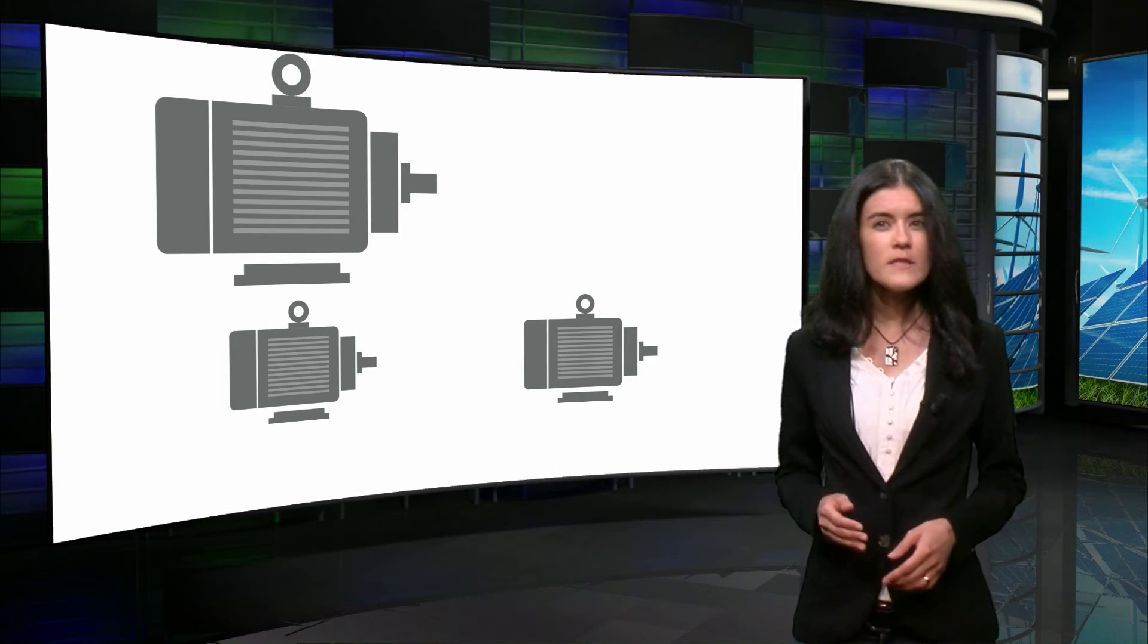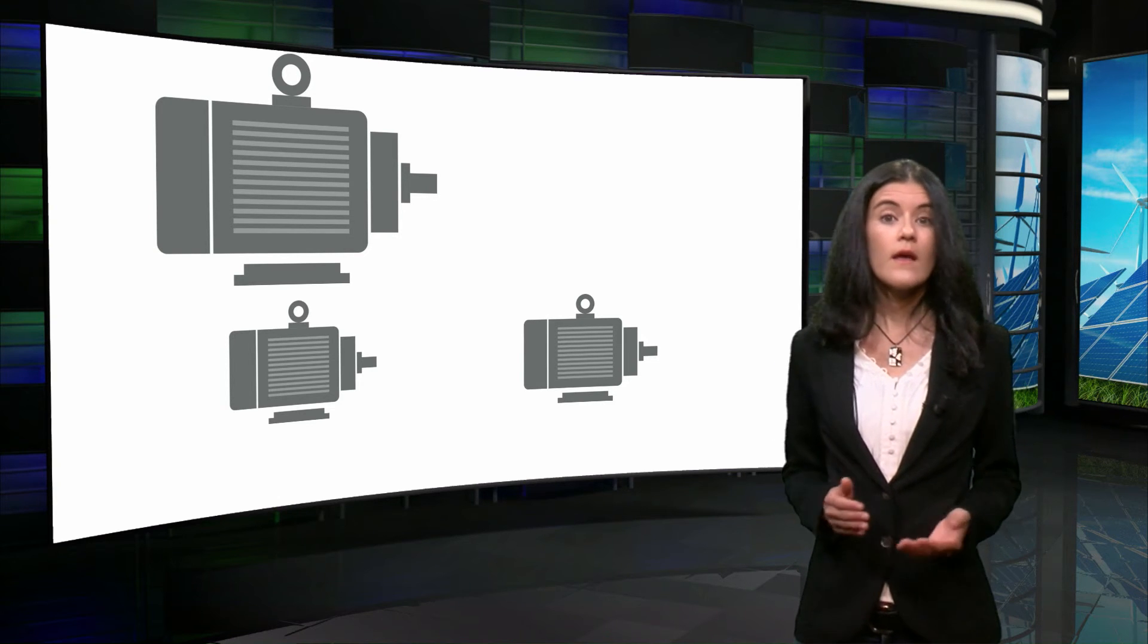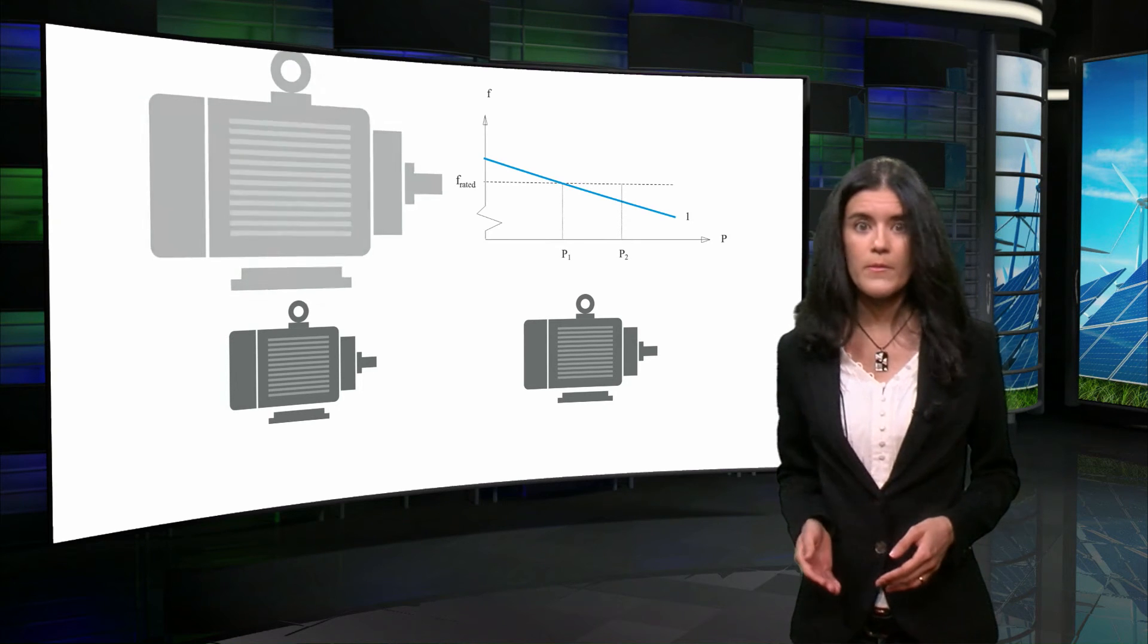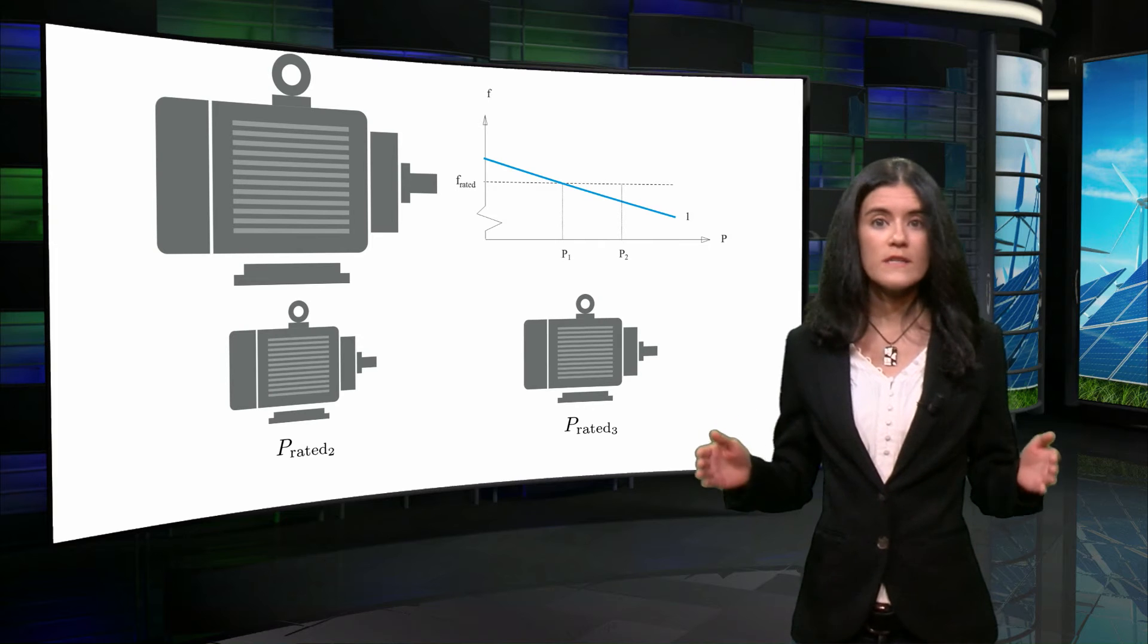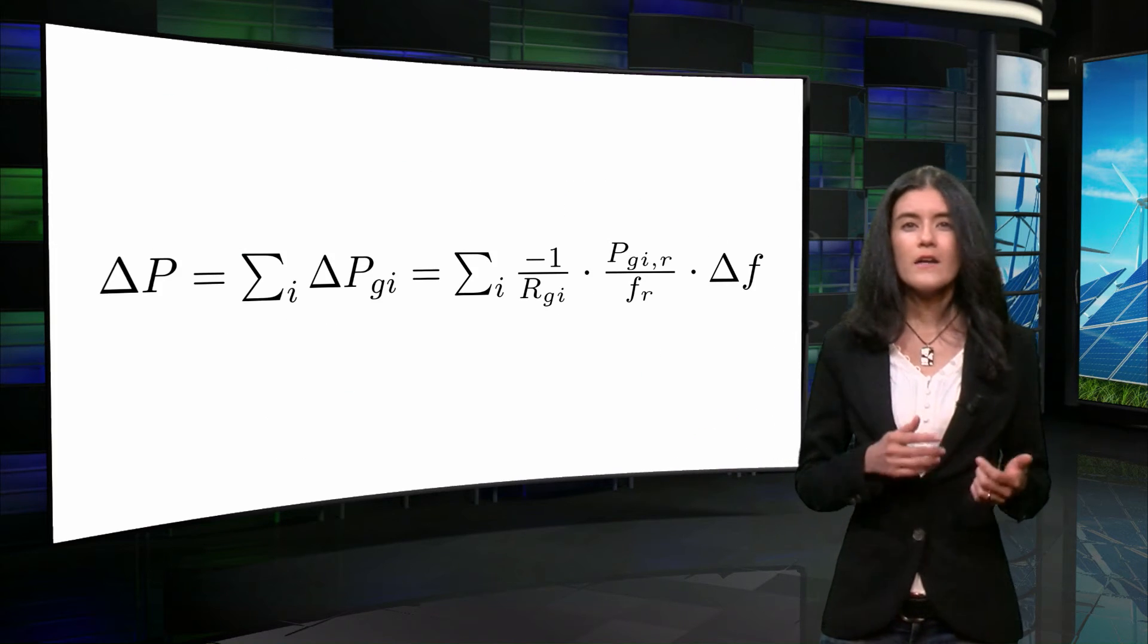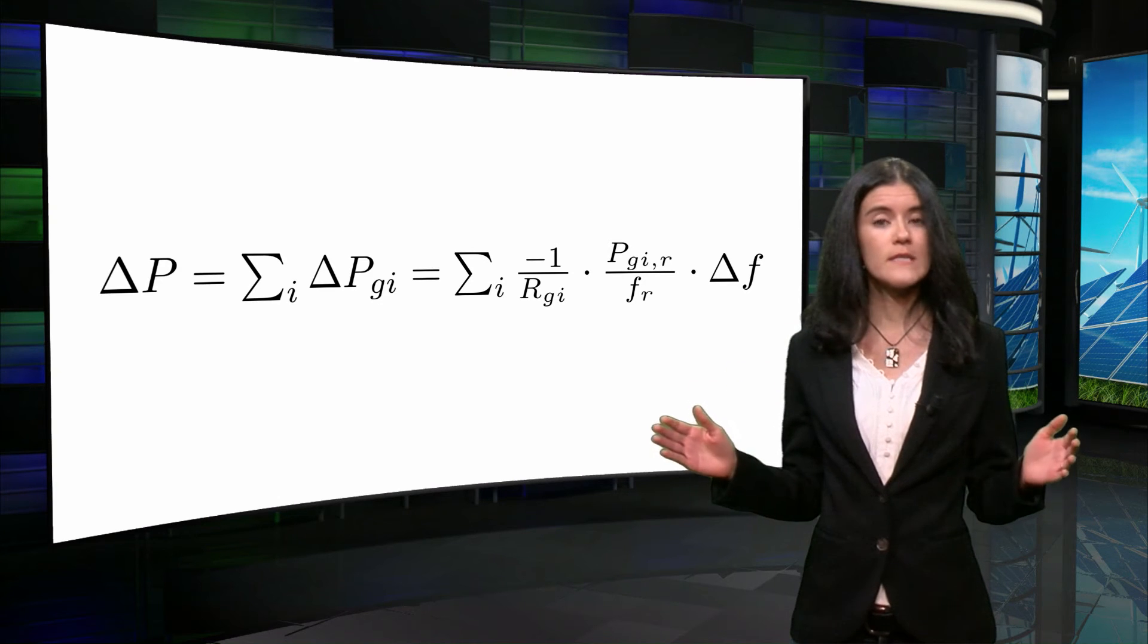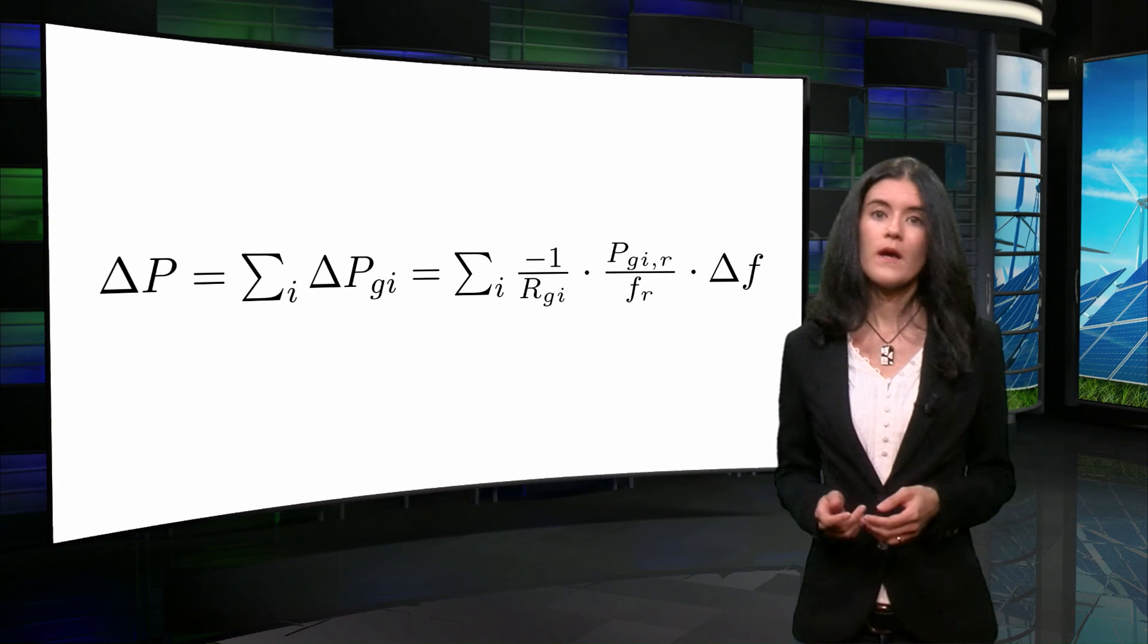For a multi-generator system, the network power frequency characteristic, given by lambda, is determined by the droop of the primary active power controls, and the nominal rated power of all generators in the system. In such case, a change in active power consumption is made by all generators in the system, given as the combination of all droops, as shown in the equation.